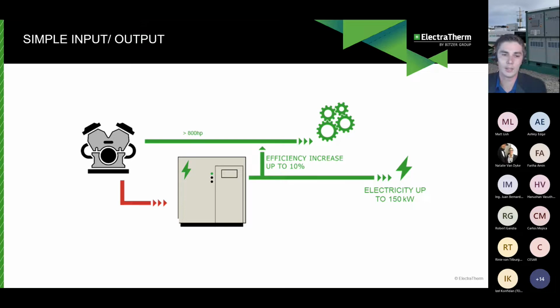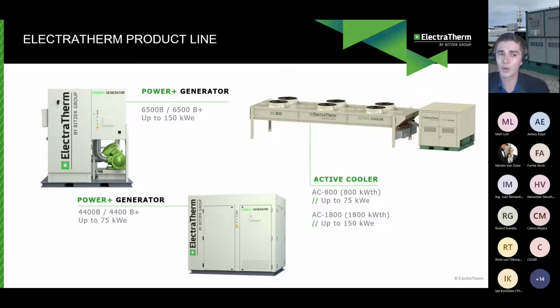But it's simple, and this heat comes to the system in a variety of ways, which we'll look at in a bit. Our current product line consists of 3 main products and then several more in development. Currently our largest single system is our 6500B and B plus units, which produce up to 150 kilowatts gross. That's at 60 hertz. And then our 4400B systems produce up to 75 kilowatts. And then our active cooler, which we'll get into in a lot of detail. Our active cooler is designed to reject roughly 800 kilowatts of thermal energy and greater, and it's based off the platforms of those other 2 existing systems.